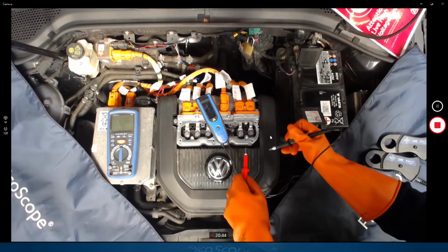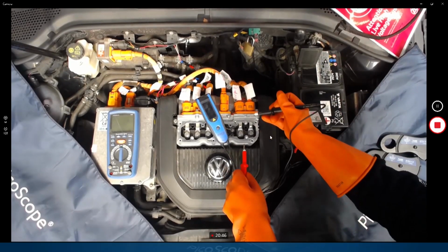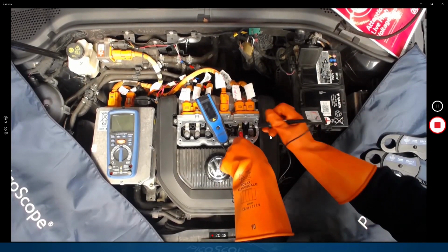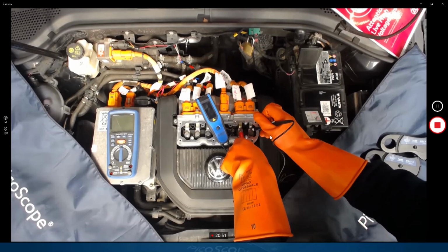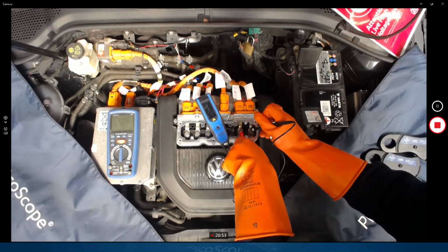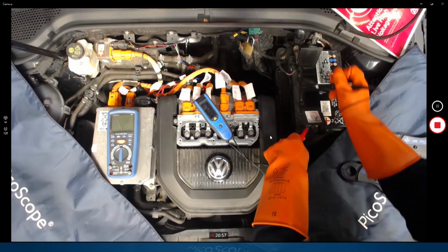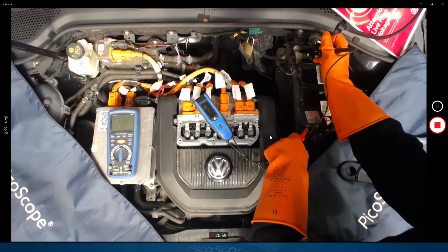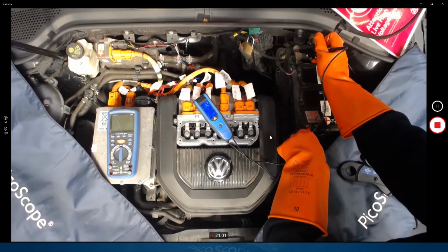There we have it, we can still read 12 volts. We go now to our test point, the actual DC cables coming into the inverter. Touch the probes across that, and there we have nothing on the screen, indicating an absence of voltage. We go back to our known voltage source to check we can still measure a voltage, which we can - still 12 volts.